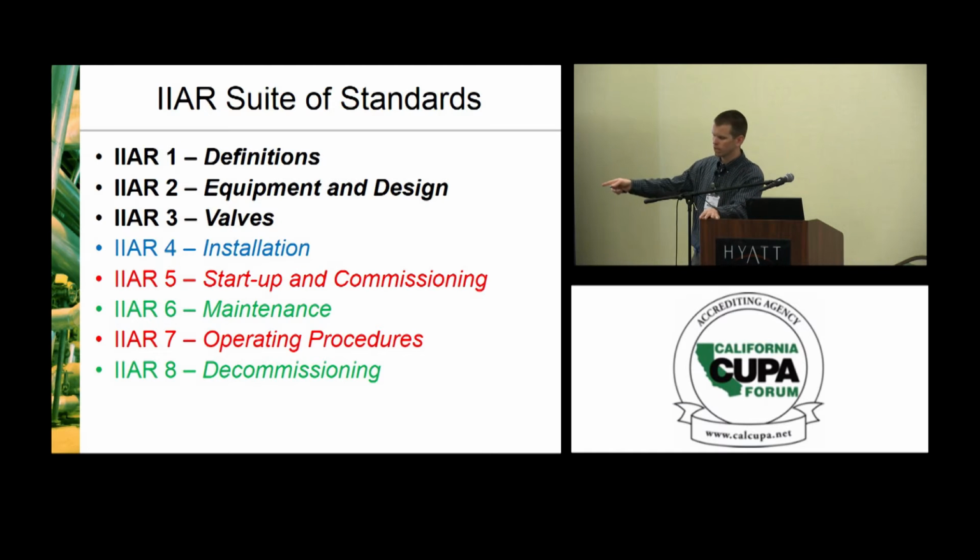Yes. I'll answer your second one first, and the answer is no on the threads. It's a standard pipe thread on an ammonia system. Typically, I haven't seen any backwards or unique threads in general. So that's the easier one to answer. As far as the governing body on pressure vessels, a pressure vessel in an ammonia system needs to be in accordance with the ASME Boiler and Pressure Vessel Code, Section 8. So that would be the governing body.